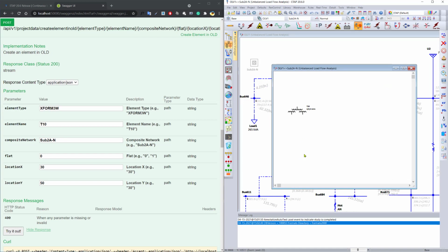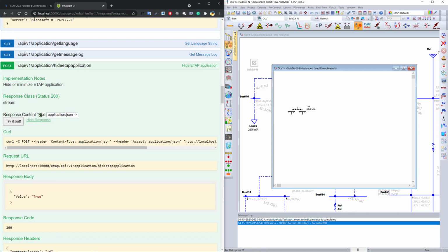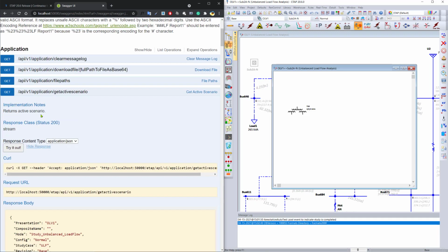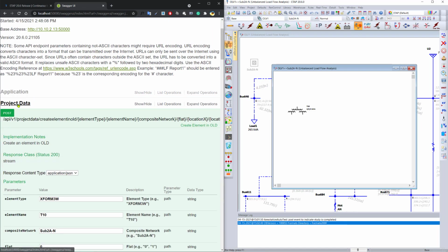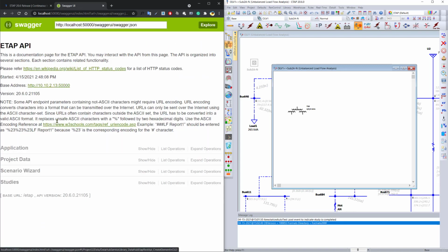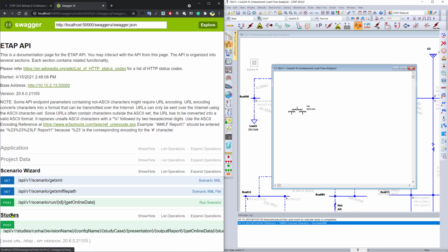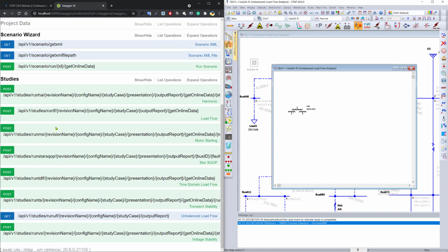So with this expansion in ETAP 20.6 in the ETAP API and the Python scripting capabilities, you can not only look at the information about the project itself, the application, but you can also manipulate project data, manipulate the scenario wizard, and of course perform various studies such as load flow, short circuit, motor starting, star sequence of operation, time domain, transient stability, voltage stability, and so on, giving you maximum control over ETAP and automation that you would like to implement.